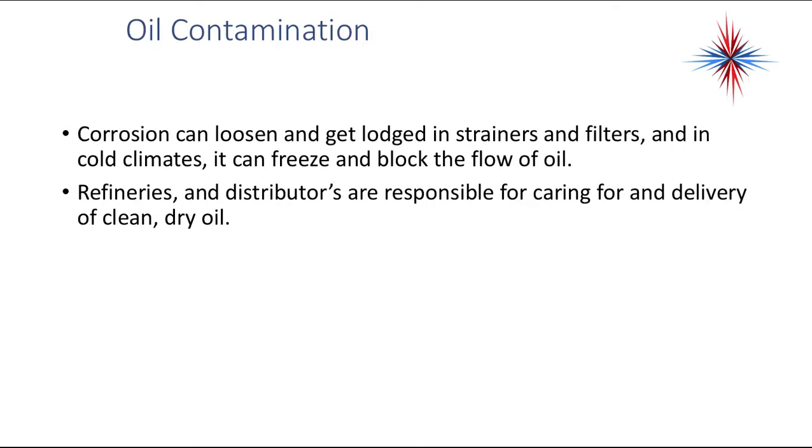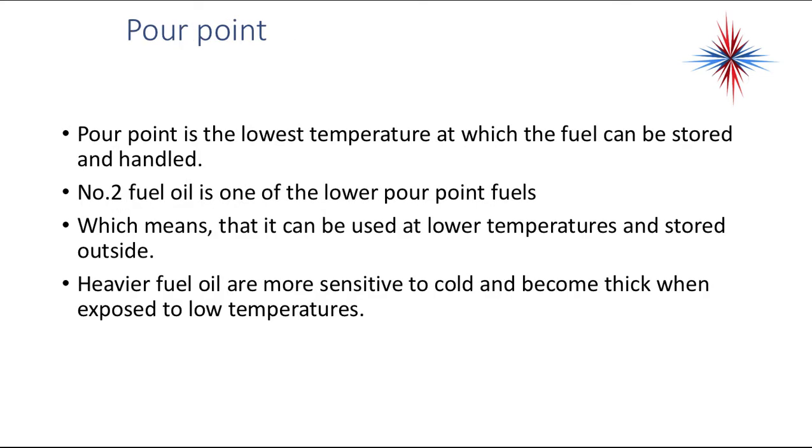Oil contamination is another property. Corrosion can loosen and get lodged in strainers and filters, and in cold climates water can also freeze and block the flow of oil. Refiners and distributors are responsible for caring for and delivering clean, dry oil.